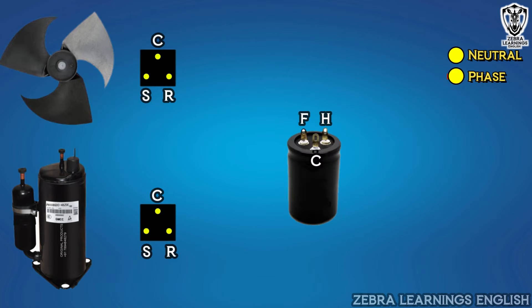Now, one terminal from the phase should be connected to the common of the capacitor. Then, connect from this common terminal to the running terminal of the compressor and the running terminal of the fan motor.